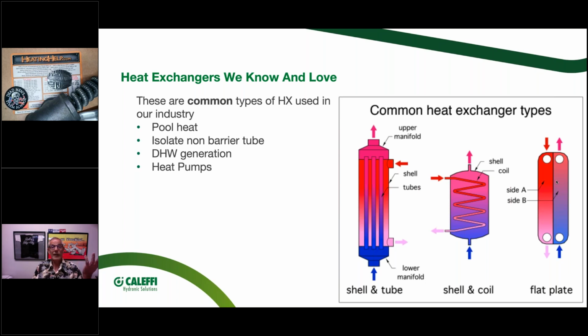Now, you'll get a call on the phone that, I'm just not getting the amount of hot water out of my mod con. Boilers are famous for this. Over time, the performance of the hot water drops off. It means the heat exchanger could be fouled. Got to run a cleaner through that, clean that hard water buildup. So those are some of the things they cautioned about.